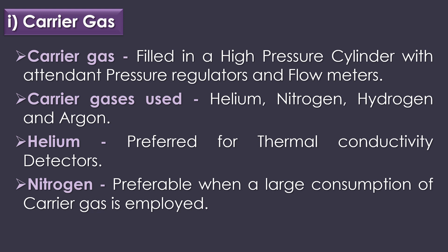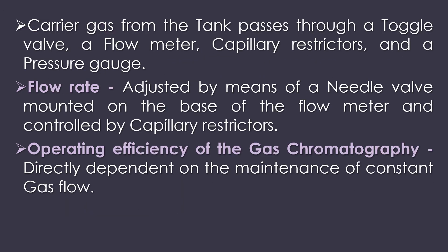The first part of gas chromatography is the carrier gas, which is filled in a high pressure cylinder with pressure regulators and flow meters. Helium, nitrogen, hydrogen, and argon are used as carrier gases. Helium is preferred for thermal conductivity detectors because of its high thermal conductivity relative to most organic vapors. Nitrogen is preferable when large consumption of carrier gas is employed. The carrier gas passes through a toggle valve, flow meter, capillary restrictors, and a pressure gauge. The flow rate is adjusted by a needle valve and controlled by capillary restrictors; operating efficiency is directly dependent on maintaining constant gas flow.